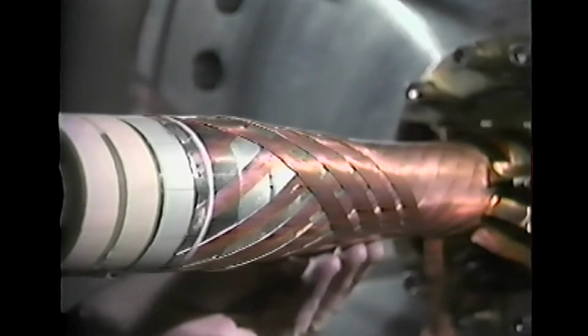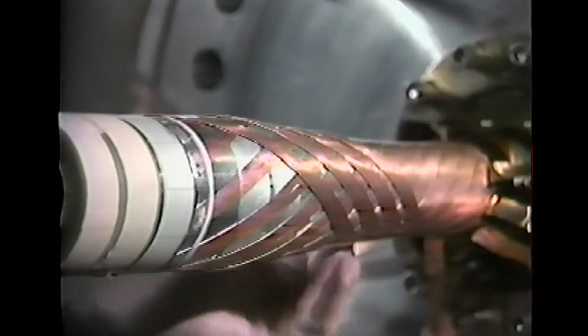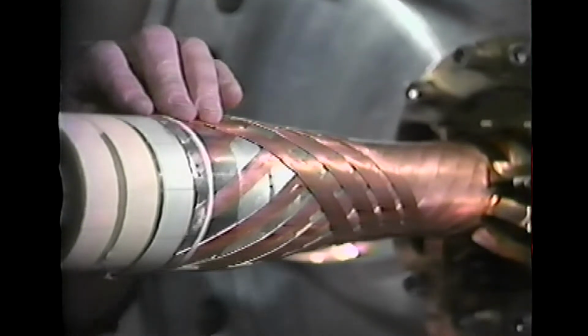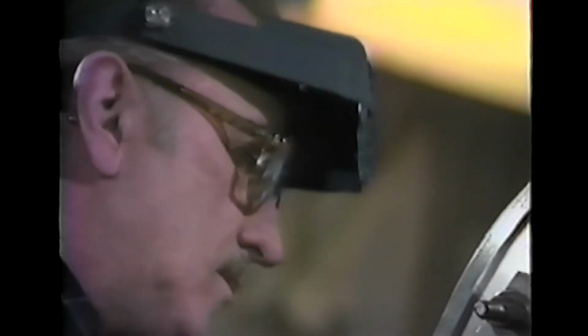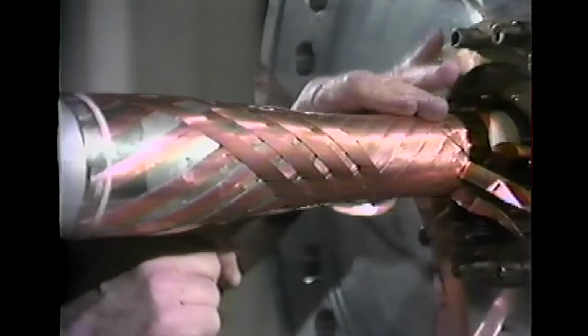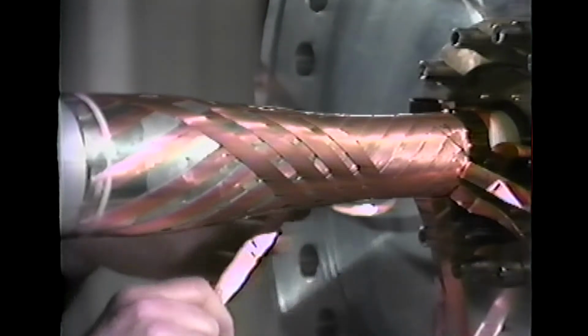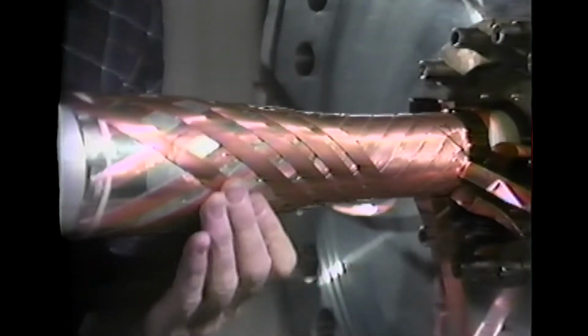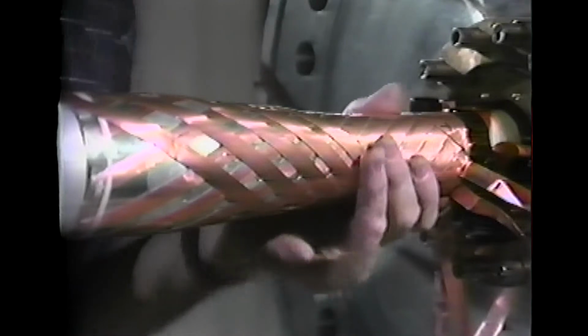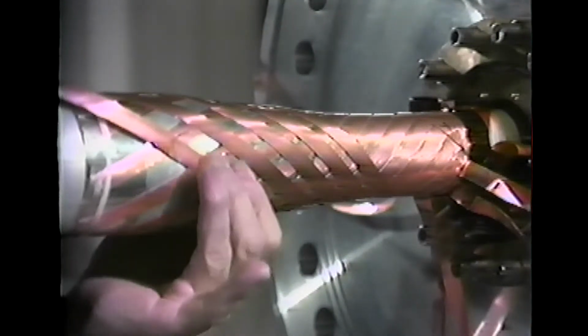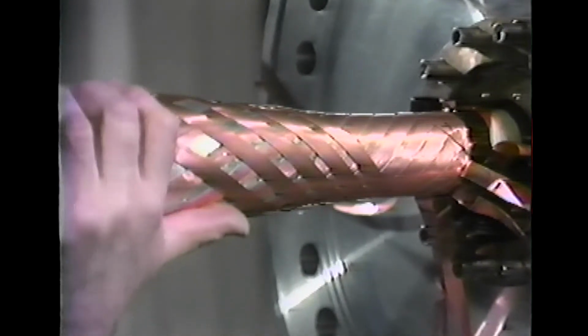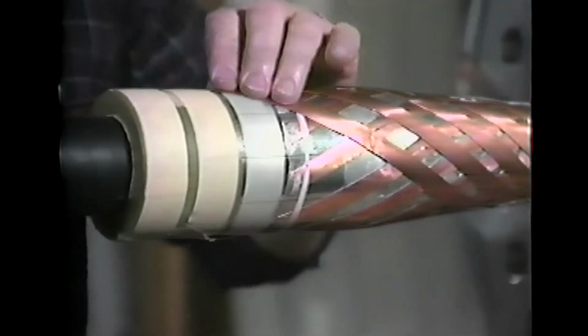The superconducting cable has both inner and outer conductors, which are designed to carry equal currents but in opposite directions. Each conductor consists of 4 layers of tape, a pair of superconducting tapes and a pair of copper tapes. Copper tapes are provided to carry current if for some reason the superconducting tapes pass out of the superconducting regime. This can happen, for example, when the network is accidentally short-circuited and very heavy currents, perhaps 10 times the normal value, may flow briefly.